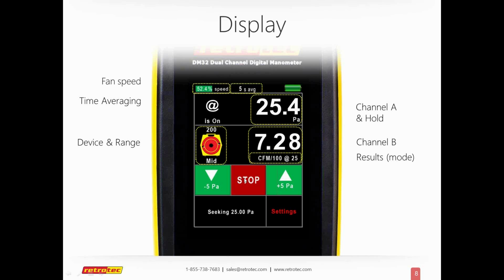And obviously I can hit stop to stop the test. I can move up or down 5 pascals. So I can actually do a range or a multi-point kind of test, getting the results on channel B as I move up and down. And at the bottom it's telling me that I'm seeking 25 pascals, so I know what pressure I'm trying to achieve at the top.